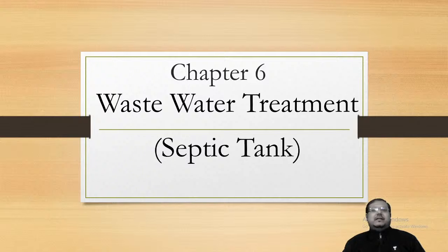सेप्टिक टैंक generally, a single septic tank can serve up to 300 persons, and greater than 300 persons a septic tank will not be able to serve. Imhoff tanks can serve it, but nowadays the concept of the Imhoff tank is obsolete. Instead of putting one septic tank, more numbers of septic tanks are being kept.